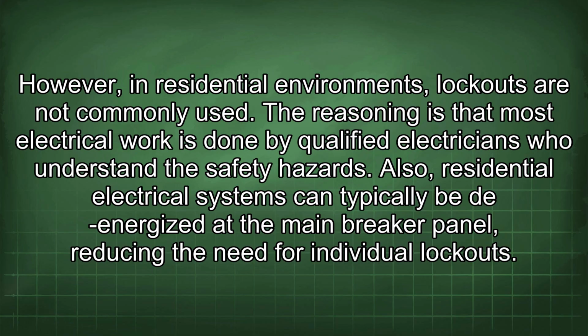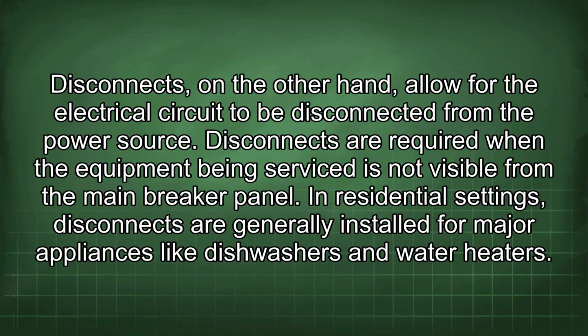The reasoning is that most electrical work is done by qualified electricians who understand the safety hazards. Also, residential electrical systems can typically be de-energized at the main breaker panel, reducing the need for individual lockouts. Disconnects, on the other hand, allow for the electrical circuit to be disconnected from the power source. Disconnects are required when the equipment being serviced is not visible from the main breaker panel.